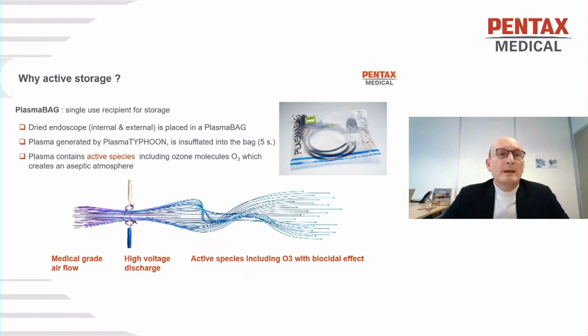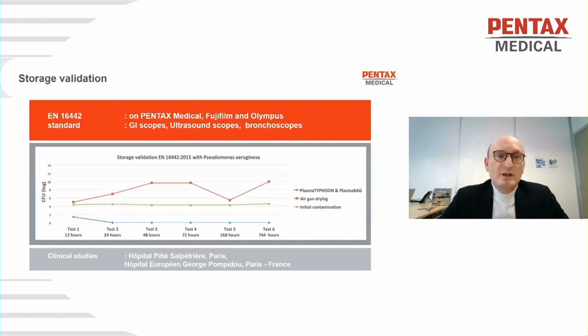So regarding the storage validation, once again, we use the European standard 16442 on Pentax Medical, Fujifilm, and Olympus devices. We also tried GI scopes, ultrasound scopes, and bronchoscopes. The protocol is very complex. We have artificial contamination of the scopes with Pseudomonas aeruginosa. So we have this level, the green line, and the system is validated if after the storage, the microbiological counts are under the green line.